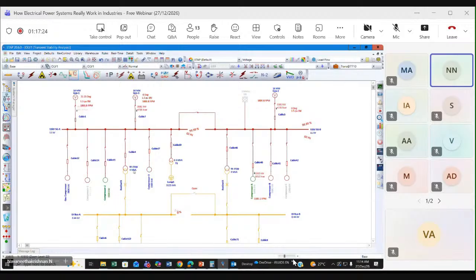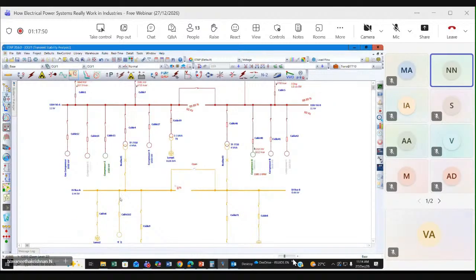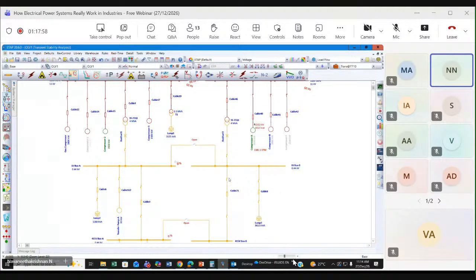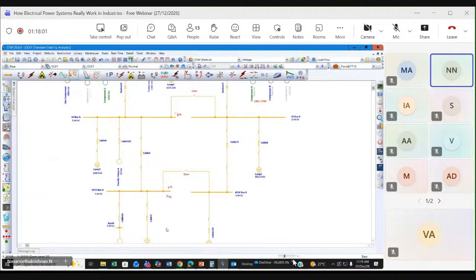In some locations it is very difficult to get a different voltage. So from a cost point of view, sometimes even the 4 MVA transformer is huge. From this design point of view, we have selected this 4 MVA transformer. We have some compressors running here of 3.8 megawatt, and some compressors of 1500 kilowatt. This is a huge rotating load connected here, and we have the LV bus here, 415 or 440 volt. Here it is again 440 volt, section B, and some of the downstream loads are connected here.